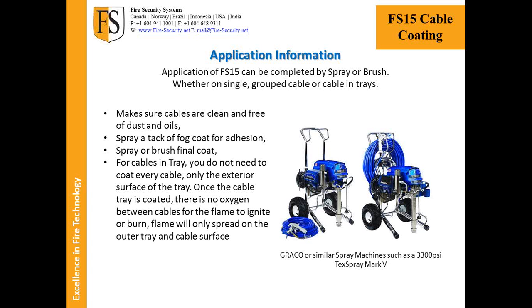How long does that take to cure? By the time you finish your fog coat, you're ready to spray your heavy coat. It would take maybe possibly an hour, if that, for a micron thickness fog coat to cure. It's only an adhesion coat. And then after that fog coat, you spray your final coat. Like I said, in the tops of trays, you don't really have to put a fog coat down. You can easily put 1.3 millimeters wet film thickness down, and then it will cure to the 1 millimeter.